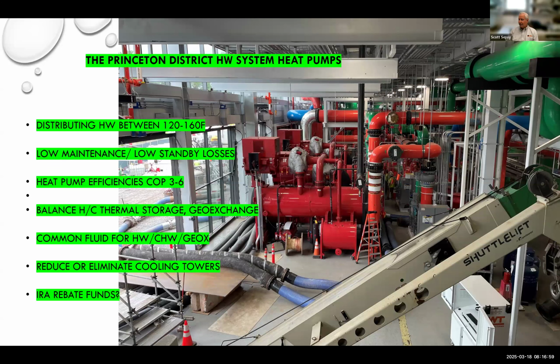Now, instead of sending the heat into the sky through our cooling towers, we reject the heat into the ground and store it for use in the winter. For short-term imbalances between heating and cooling, we use our thermal storage tanks. Over the course of a year, we charge our geo-exchange fields with rejected heat during the summer and pull that heat out in the winter. And during the shoulder seasons, as I mentioned, the COPs can get up to 6.